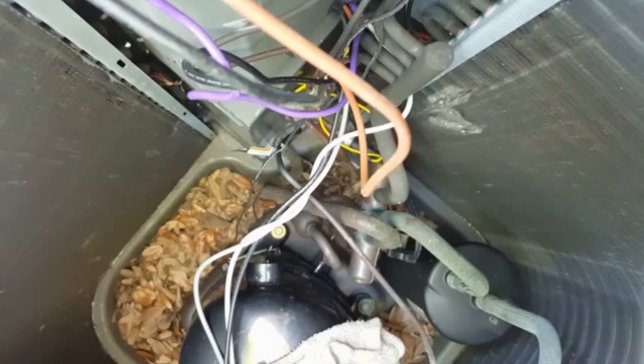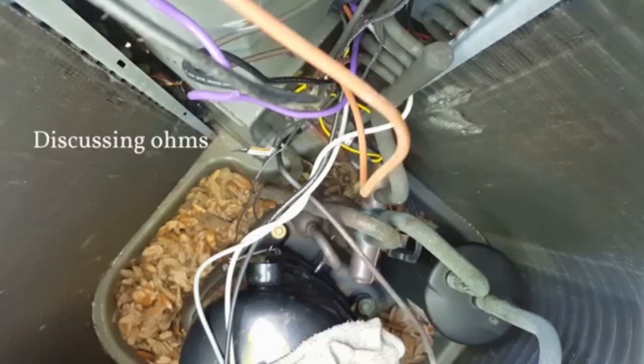I was kind of wondering that myself, because once I turned it off here and looked down at the relay, you see it's energized whenever it's running. It wasn't energized. So something has gone wrong inside. Okay. Cool. And the fan's receiving power. That's why it was running slowly as well. It's getting like a backward signal of charge, electricity from a different place. But I didn't know if you wanted it that way or if you wanted it in the on position. You can leave it off. It's fine. When I put the meter on the leads that are going to the compressor, it showed that there was no connection inside. So I'm trying to see why it's saying that. Because it's supposed to be a degree of connection, so to speak. Right, okay.